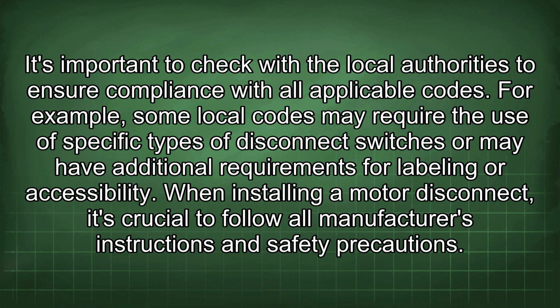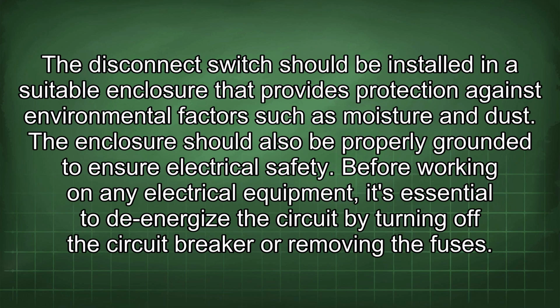For example, some local codes may require the use of specific types of disconnect switches or may have additional requirements for labeling or accessibility. When installing a motor disconnect, it's crucial to follow all manufacturer's instructions and safety precautions. The disconnect switch should be installed in a suitable enclosure that provides protection against environmental factors such as moisture and dust. The enclosure should also be properly grounded to ensure electrical safety.